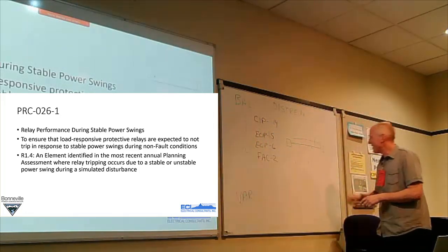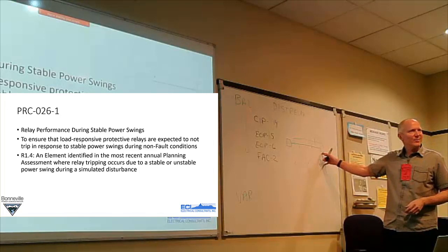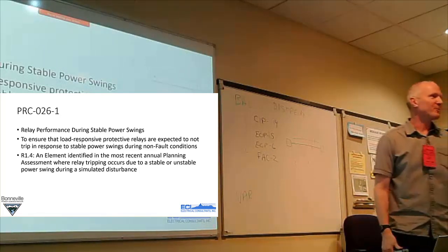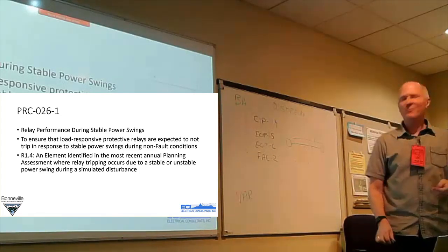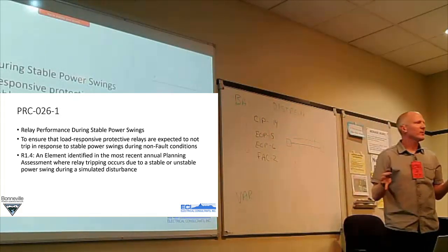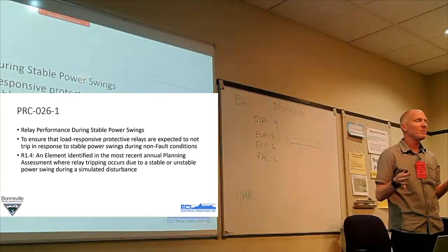Not a fault. Within somebody's system, you can take a transmission bus and put a really big honking load here, which looks a lot like a fault, but it's just a load. It was a 15 gigawatt load. And then some relays over here played. At least we knew the distance relay could function in that way, that if there was a big enough swing, other relays would play.